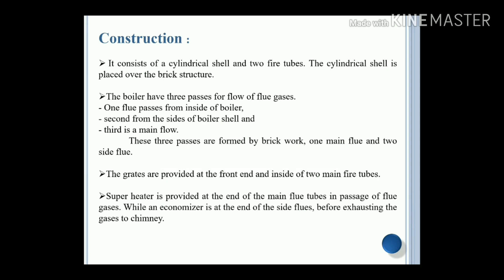The boiler has three passes of flue gas flow: the first passes from inside the boiler, the second from the side of the boiler shell, and the third is the main flue. These three passes are formed by brickwork - the main flue and two side flues. Grates are provided at the front and inside the two main fire tubes. A superheater is provided at the end of the main flue tubes in the passage of flue gases, while an economizer is at the end of the side flues before exhausting gases to the chimney.